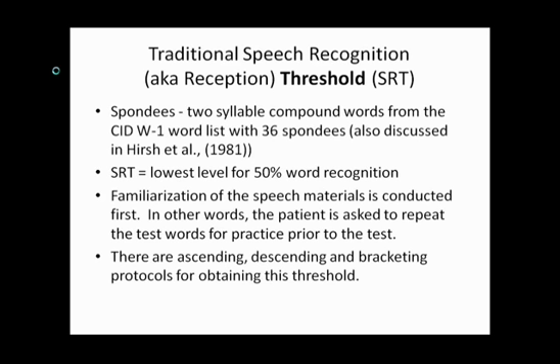The traditional speech recognition or reception threshold uses spondees — two-syllable compound words from the CID W1 word list with 36 spondees, also discussed in the Ira Hirsch 1981 paper. The SRT is the lowest level for at least 50% word recognition ability. Familiarization is conducted first: the patient repeats test words for practice — 'pancake,' 'baseball,' 'cupcake.' There are ascending, descending, and bracketing protocols for obtaining this threshold, and unfortunately there is no standardization for that procedure.